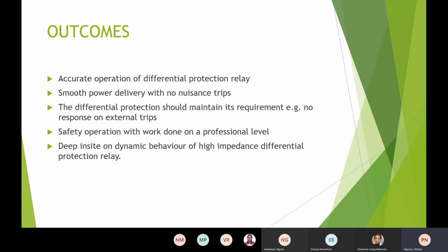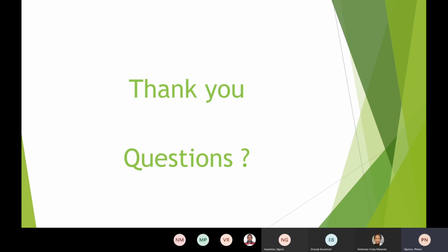That is one of the outcomes that they are expecting to see, and as I am working on this, I am expecting to make sure that this is delivered accurately, and that the relay operates the way it is supposed to, without affecting other equipment. It operates in its region. Smooth power delivery with no nuisance trip. The differential protection should maintain its requirement: it must not trip from the external operation, and safe operation that does not impose risk on other equipment and personnel who are around. And also the insight on the percentage. Thank you. If there is any question, I would like to have them and answer them.